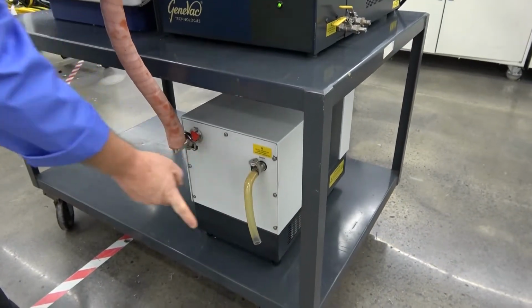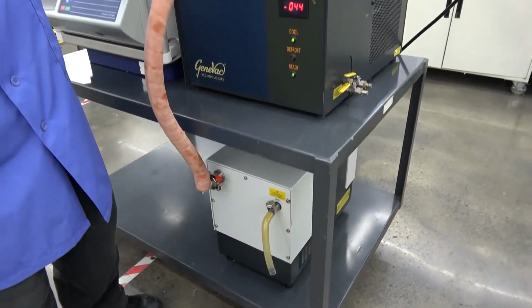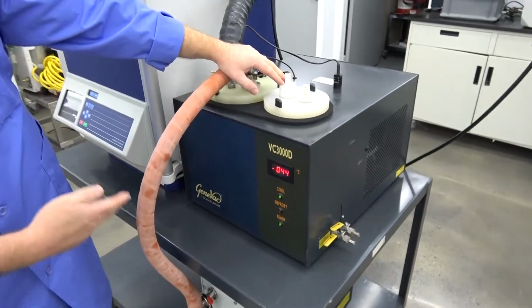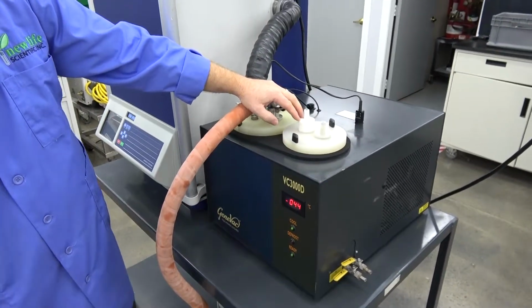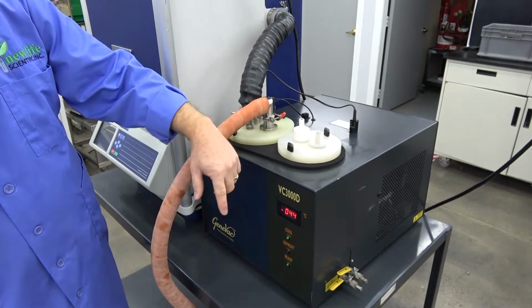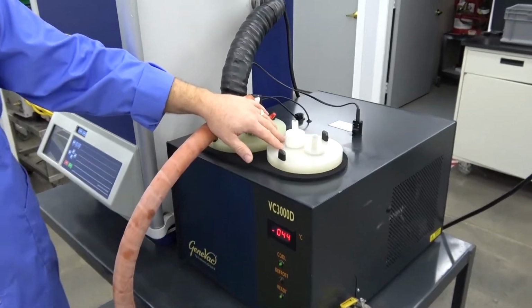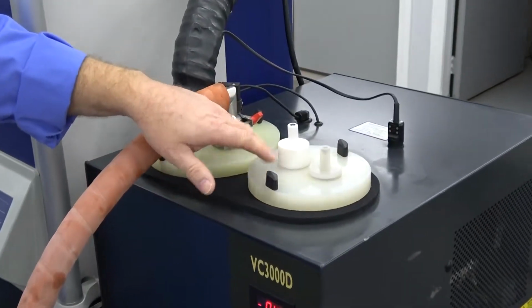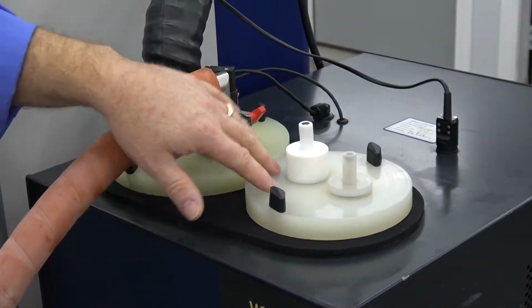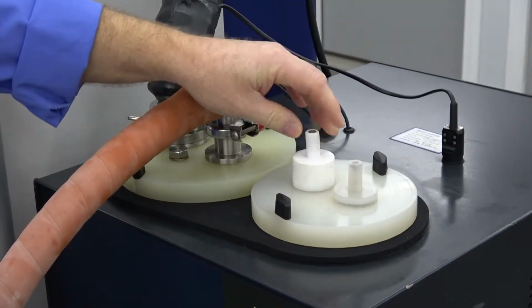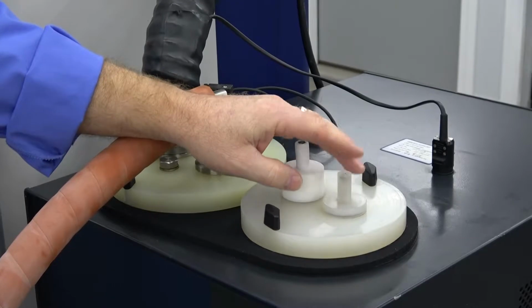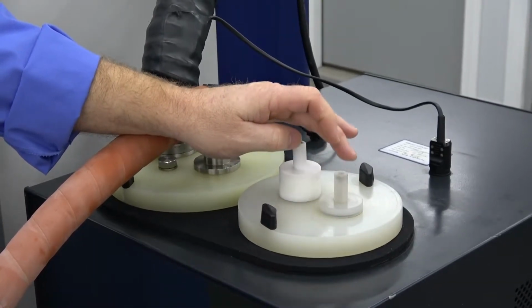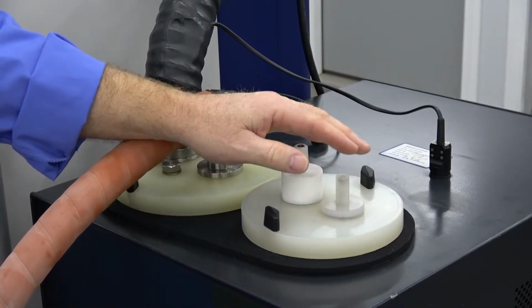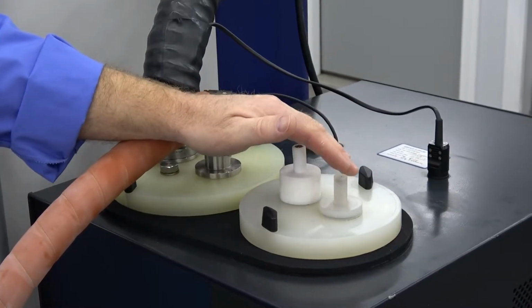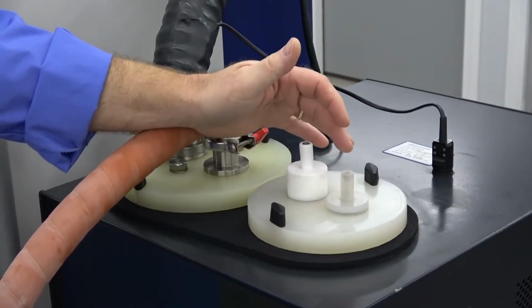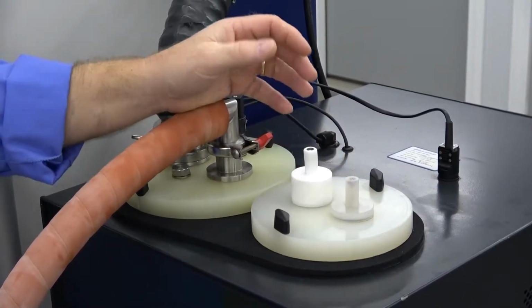Essentially you can hook a hose, bring it back up to the condenser port, and filter some of that exhaust coming off your vacuum pump. If you're running some extreme chemicals, it's something you might want to do. So you can run a hose up here, hook it back into this, and also run an exhaust hose out from the port here into a fume hood or outside somewhere where it's not coming into your lab.